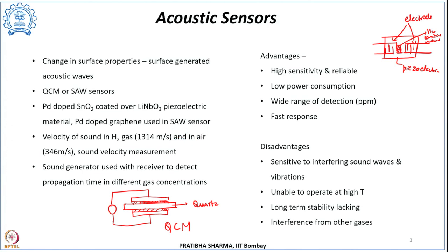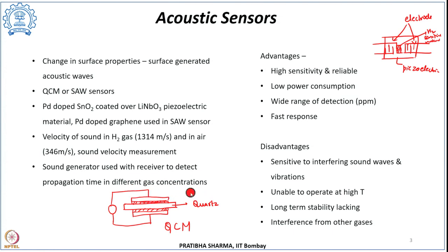Another acoustic sensing method uses the fact that the velocity of sound in hydrogen is much higher than in air — 1314 m/s in hydrogen versus 346 m/s in air. This difference can be used to measure hydrogen concentration. A sound generator and receiver are used, and the time it takes for sound to propagate at different gas concentrations is measured. This propagation time is calibrated against gas concentration to detect hydrogen.